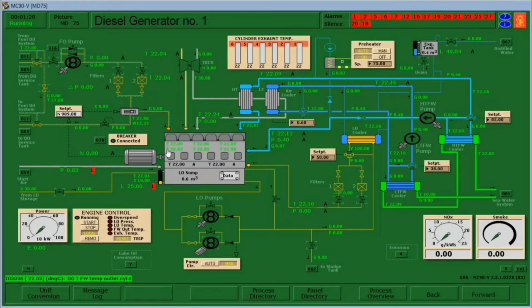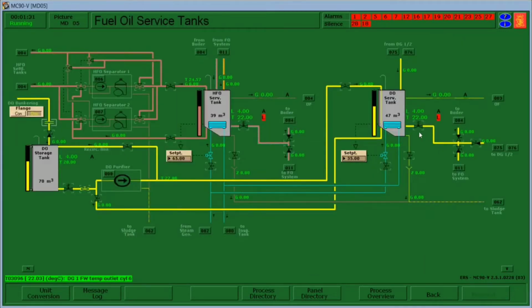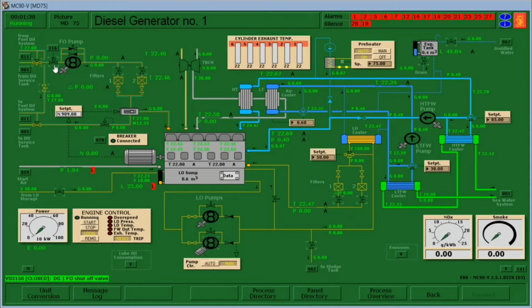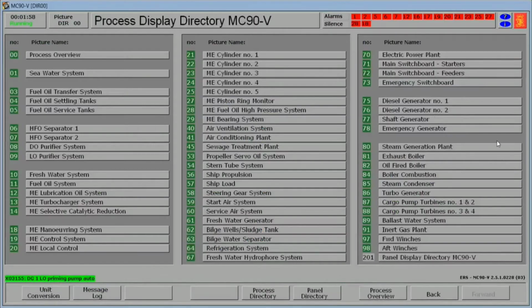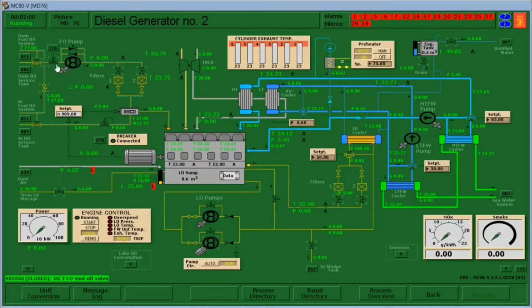Go back to diesel generator number 1 and open the fuel oil settling tanks, to boiler, fuel oil and diesel generators. Open the shut-off valve and 1 filter, same as the fuel oil, and fill up the lube oils from lube oil storage at least 40% to 70, level of 70, then close. Open the pump control to auto and click again, same process as the first one.